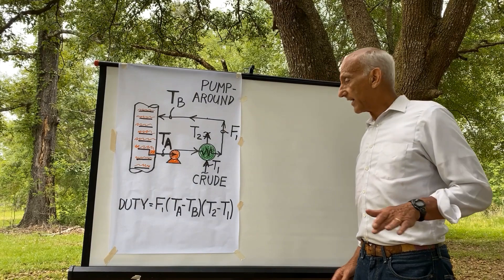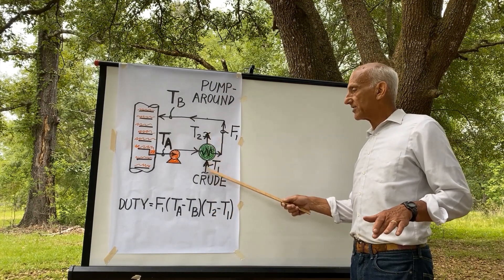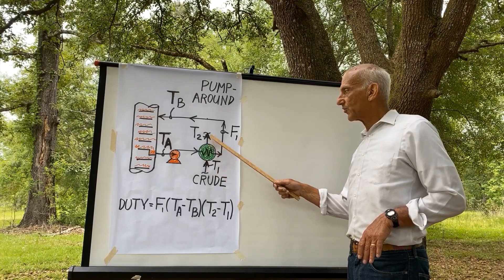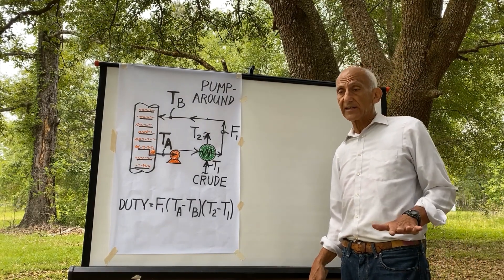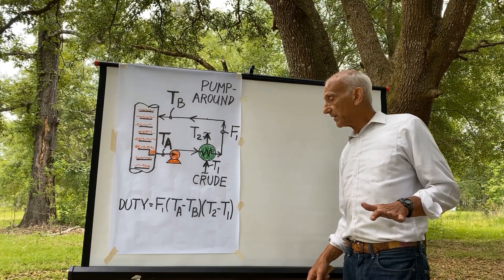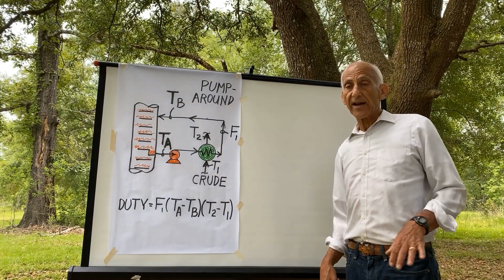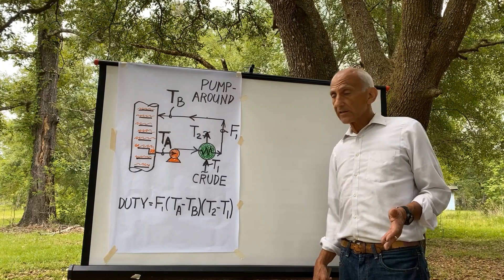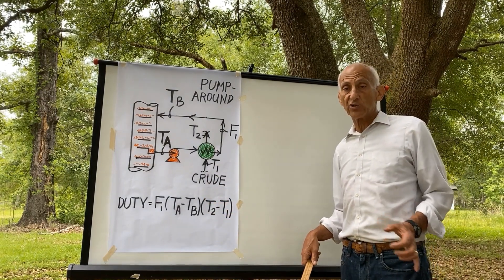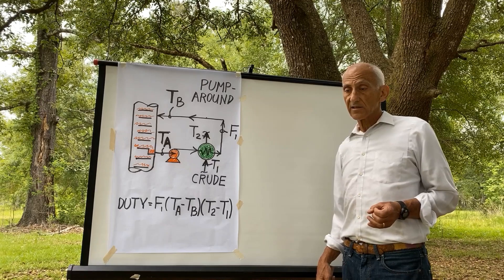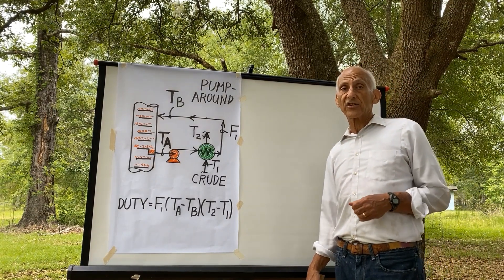So what you have to do is look at the temperature change on the crude side. If this temperature change on the crude side goes up at a constant crude rate, at a constant flow on the tube side, as you increase the pump around circulation rate — if the delta T between T2 and T1 goes up — then you are extracting more heat from the pump around, which is good. But at a constant crude rate, if the temperature difference between T2 and T1 gets smaller, then the pump around heat extraction is diminishing even though the pump around circulation rate is going up.